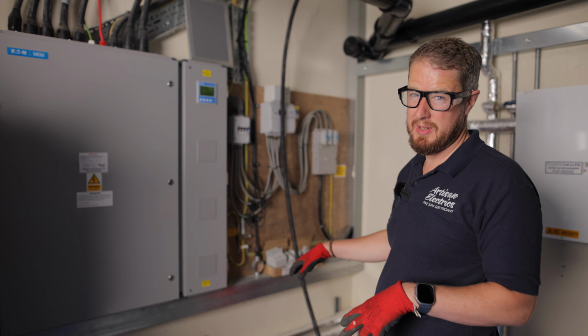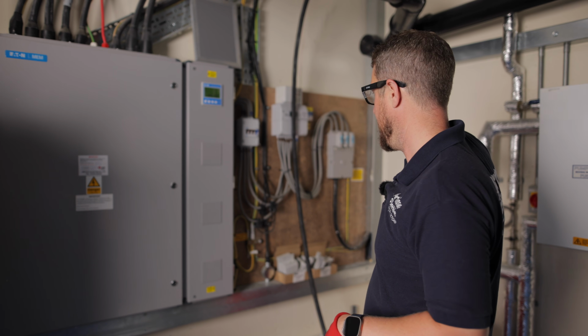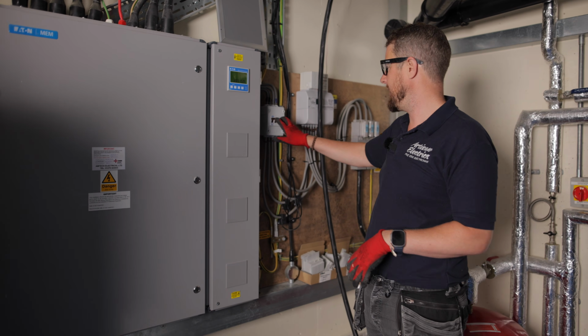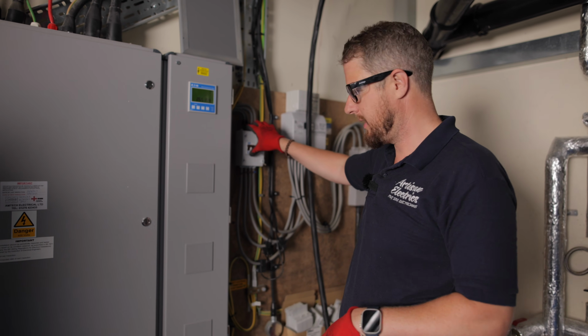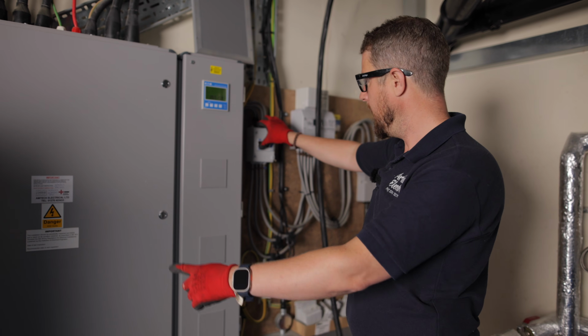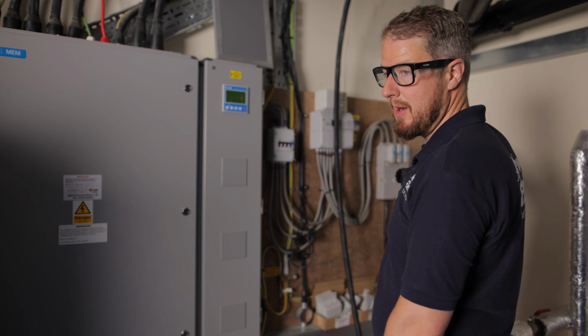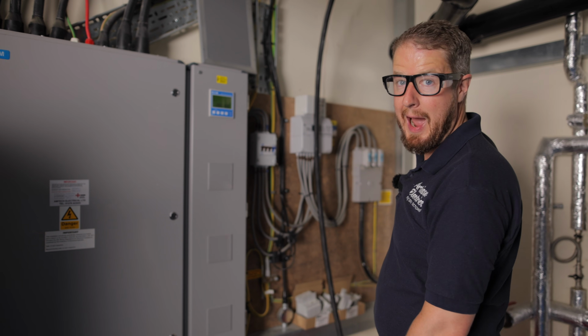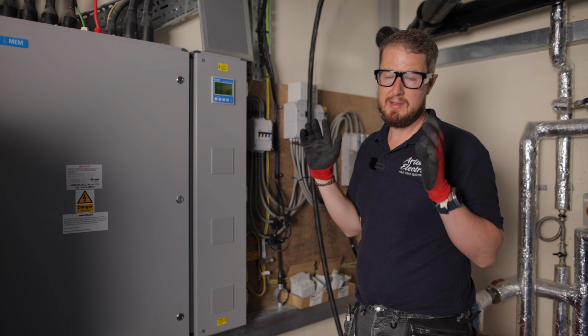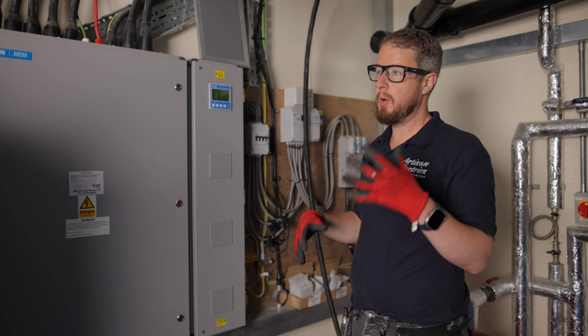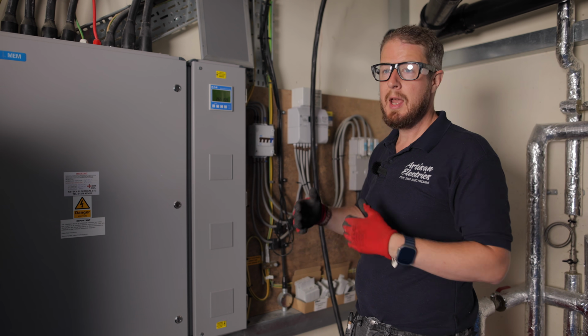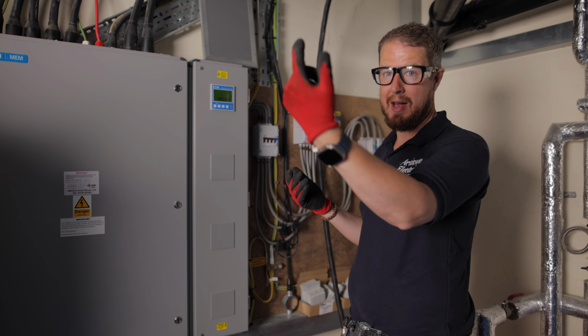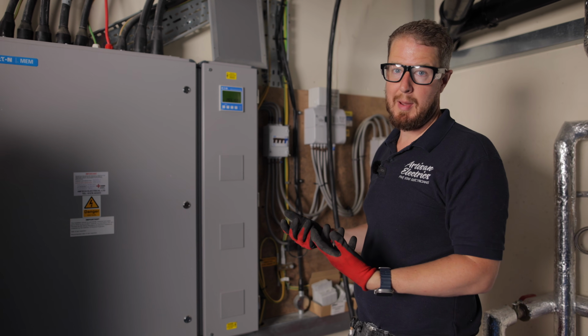So this is where the gateway's going, on the wall there. And what we've got to do is get the tails out of this main switch. They currently go into this panel board. We've got to reroute them now through the gateway. So they'll go into the gateway and then out of the gateway into the panel board. And that means the gateway is controlling the whole system, monitoring how much power the property is using and instantaneously switching over to battery power if there's a power outage.